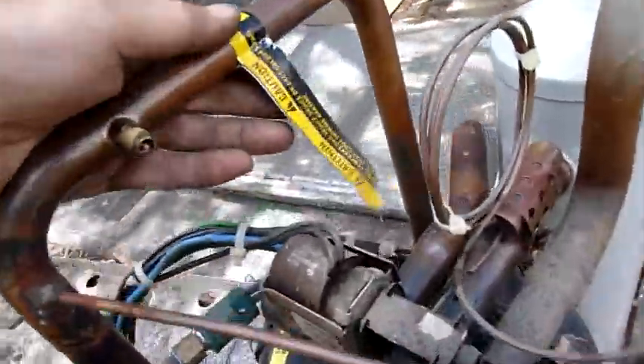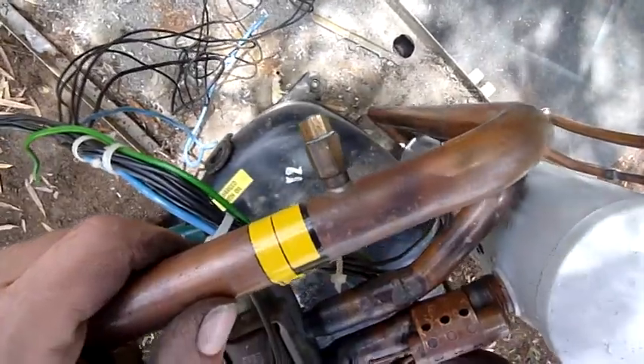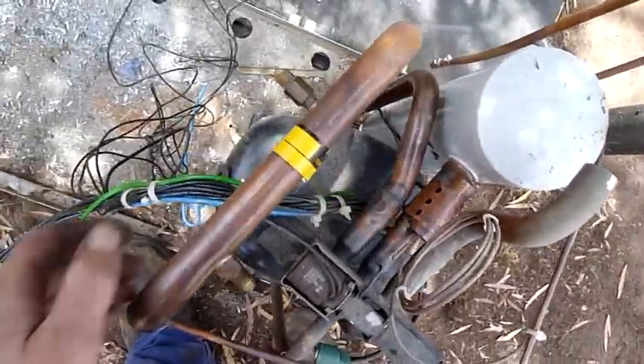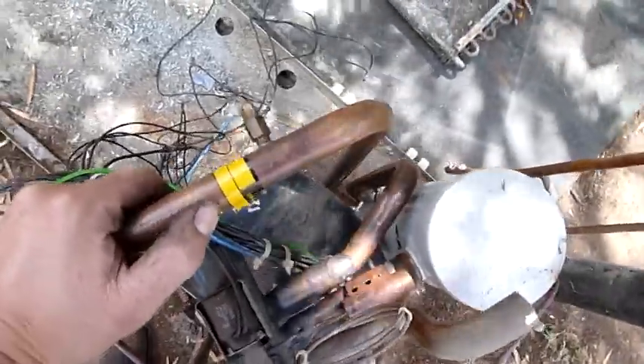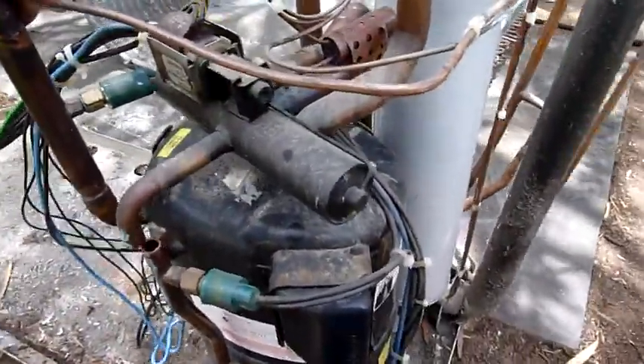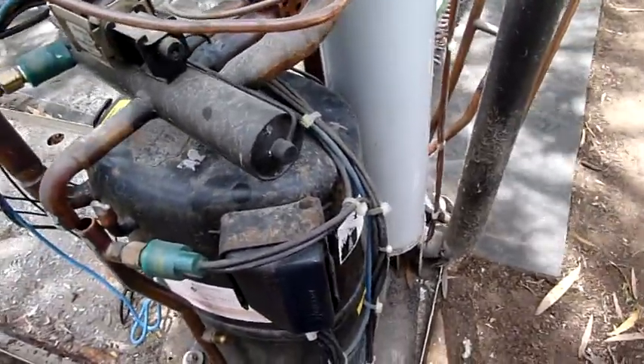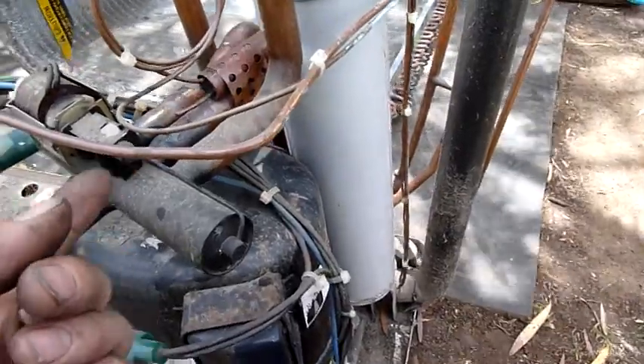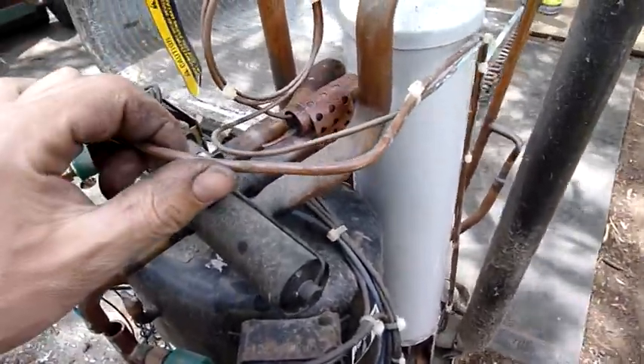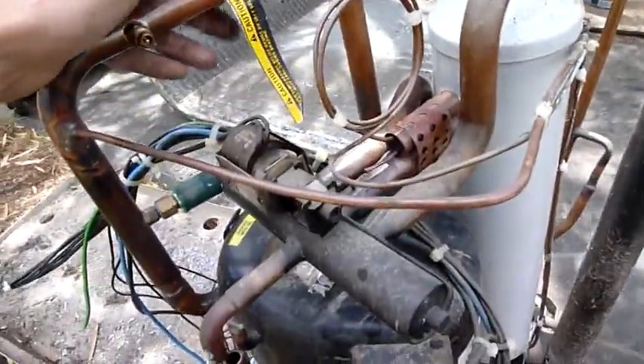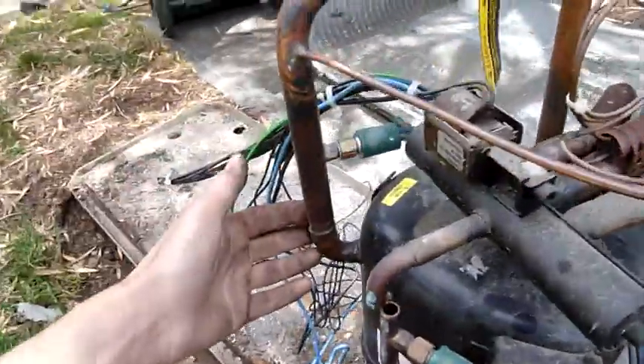Okay, before I cut this up, I just thought I'd ask, why would there be a fusible valve on the suction side? I can understand the high pressure side, but the suction side's generally cold and sweaty regardless of what mode it's in. I'd hardly expect it to melt a lead plug. And that's all that is, a little lead plug in there which melts and blows out if the system has something seriously wrong with it. I mean, the only time that'd blow out is in the event of a structural fire. If this unit was involved in a fire, that'd probably be the first thing to go. Yeah, interesting. I've seen them on liquid accumulators, like liquid receivers from the condenser, but that's to be expected. It will get high temperature liquid or vapour, vapour if it's not working properly, but why there's a blowout plug on the suction line's beyond me.